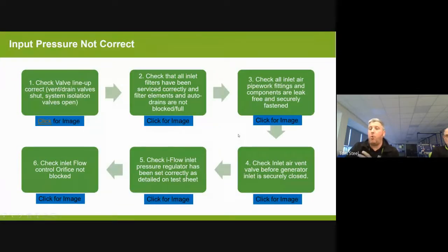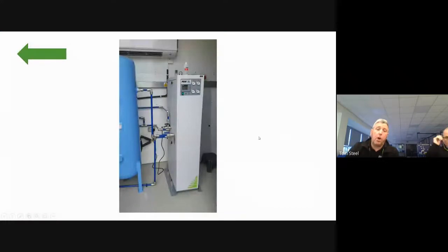We're going to check all the air inlet pipework, fittings and components are leak-free. So if we have a look at the image for this, on the generator there, we've got some pipework and lots of fittings connecting this pipework to the external tank, as well as the oxygen generator itself. We need to ensure these are leak-free. If you look at the top of the generator, you can see there's a bottle of leak detector there, and that's basically what we would use to ensure there's no leaks in the system.